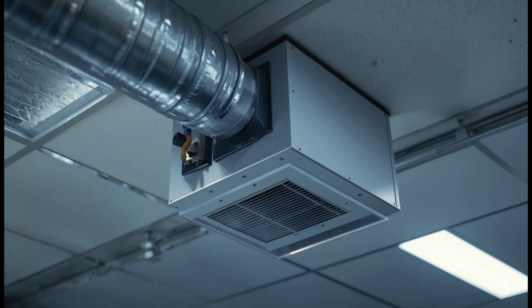To meet this need, many VAV boxes include a small reheat coil built directly into their casing, positioned just after the box's own damper, ready to add a final, modest measure of warmth to the air before it continues toward the room. Some of these reheat coils rely on electric elements, simple resistance heaters warming the air directly as it passes across them, drawing power much like the smallest space heater might.